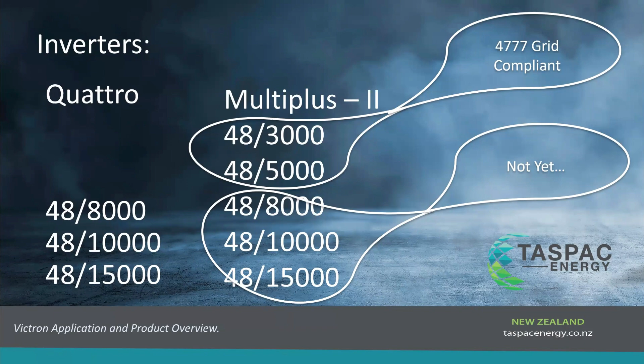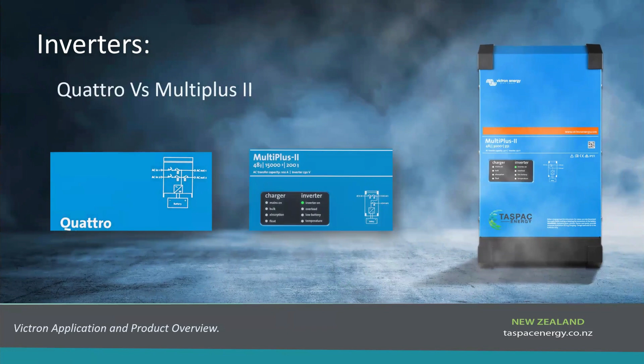The 48 8000, 10,000, and 15,000 MultiPlus-II range will eventually get grid compliance. They're just going through the hoops, as I don't know if any of you know, but it's sometimes pretty difficult to get compliance on a complex product like that. So if you're wanting to use anything that's not grid compliant, you can simply put a grid protection relay ahead of it and then rely on the grid protection relay to comply with 4777 grid requirements.